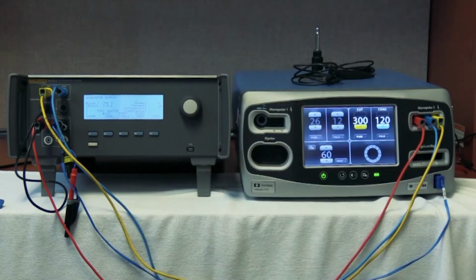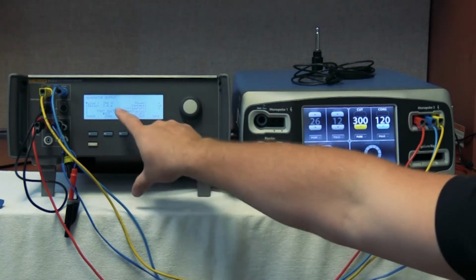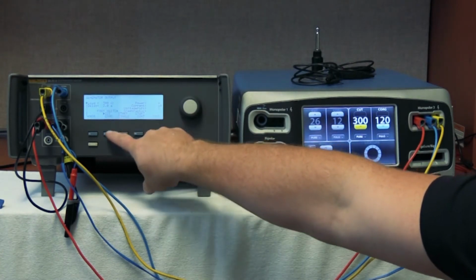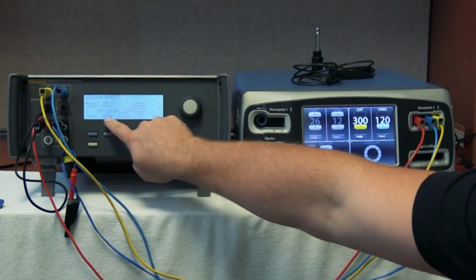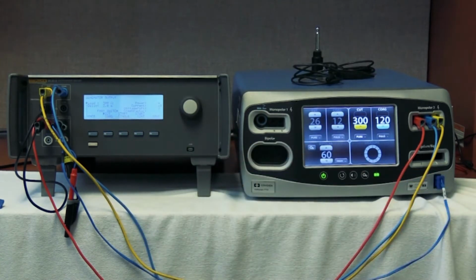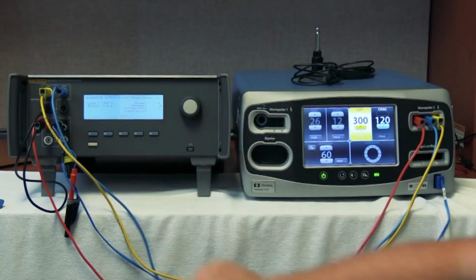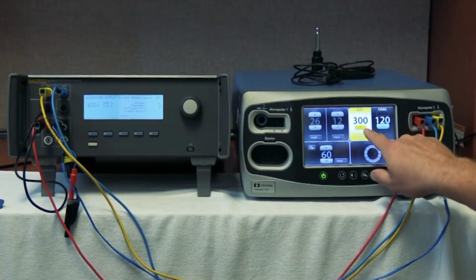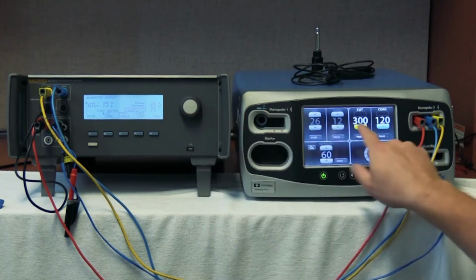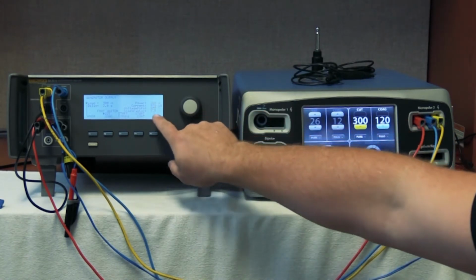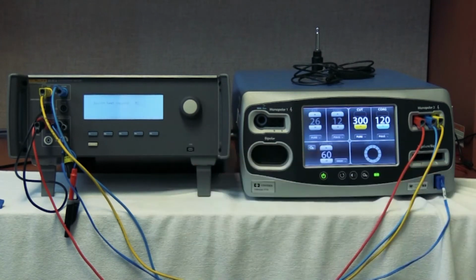Once that's done, on our foot switch, above F2 where it says foot switch, you see the arrow, we're going to toggle up to cut and push start single. Start and single will activate the cut. Here's your results: we had 300 watts, we now have 288 watts, and we can see these results. The results are saved as test 2. So there's how we test cut.